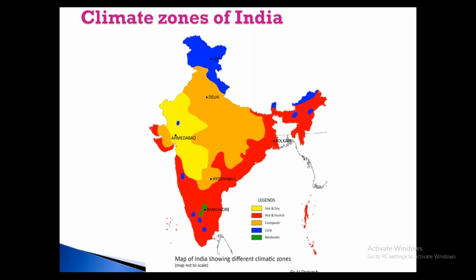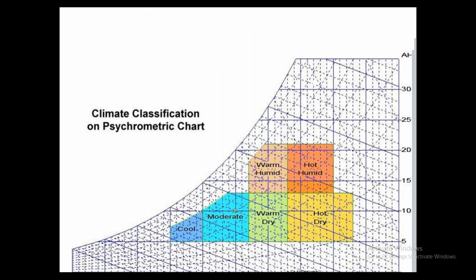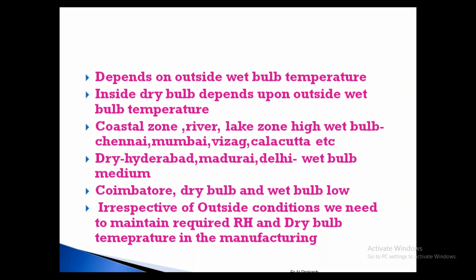So from this broad classification, you can at least visualize that it is not equal all over India. For a spinning factory, if you are running a plant of 25,000 spindles, it may not be the same for all locations. You can classify from a psychrometric chart what is a hot and humid climate. Based on the temperature graph, it will differ. Some places it will be moderate, warm, everything. The inside conditions are totally based on your wet bulb temperature. What is the outside wet bulb temperature?